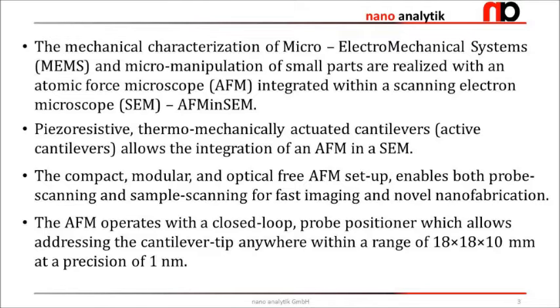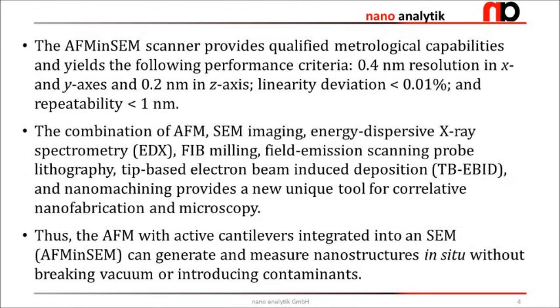The AFM operates within a closed-loop system, the probe positioner, which allows addressing the cantilever tip anywhere within a range of 18 by 18 by 10 millimeters at a precision of 1 nanometer. The AFM in SEM scanner provides qualified metrological capabilities and yields the following performance criteria: a 0.4 nanometer resolution in both X and Y axes, and 0.2 nanometer in the Z direction, linear deviation less than 0.01%, and repeatability less than 0.1 nanometers.